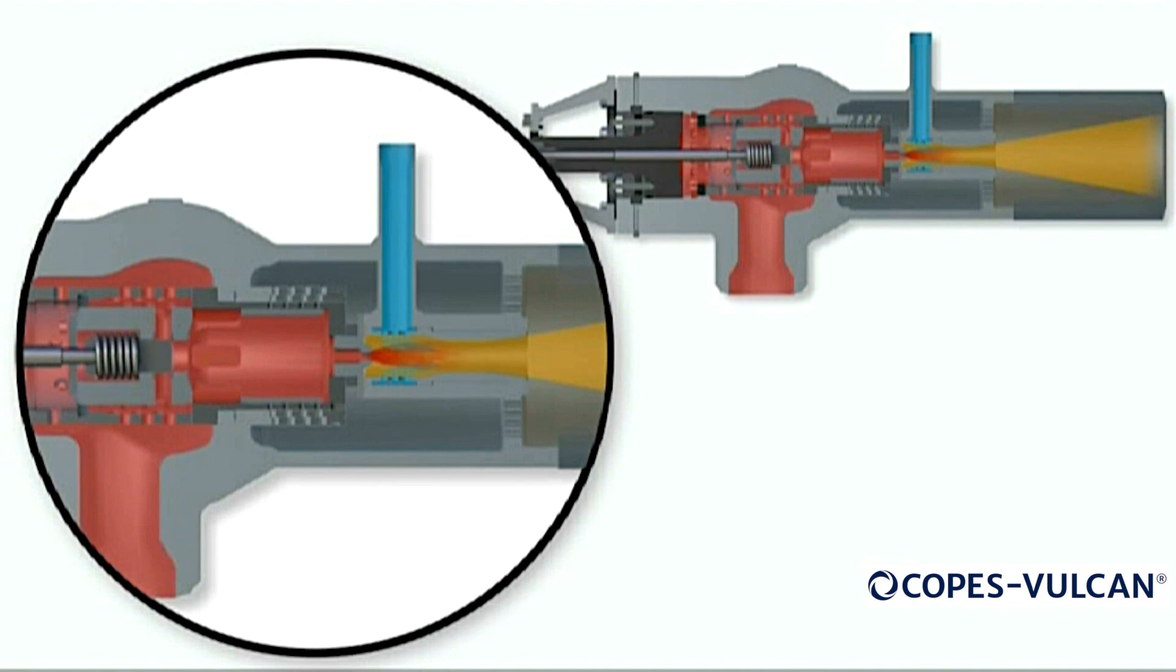At this point, full inlet steam pressure is applied to the top of the main cage, and the underside of the cage decays to downstream pressure. Effectively, the trim is now unbalanced. This unbalanced force significantly augments the seat contact load, resulting in a very tight and repeatable shutoff.